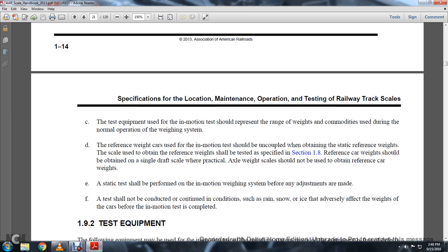The test equipment used for the in-motion test should represent the range of weight commodities used during normal operational weighing. The reference weight cars used for the in-motion test should be uncoupled, when obtaining the static reference weights. The scale used to obtain the reference weights shall be tested as specified in Section 1.8. The reference car weights should be obtained with a single draft scale; where practical, axle weight scales should not be used to obtain the reference car weights.